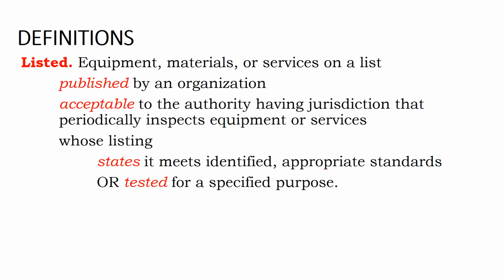That's where inspectors looking at the ground fault protection systems of inverters and seeing that they're grounded are saying, well, isn't that going to create a blind spot if there is a ground fault? And that's burnt a few buildings down on your older style central inverters. Inverters have been updating their ground fault protection systems ever since.